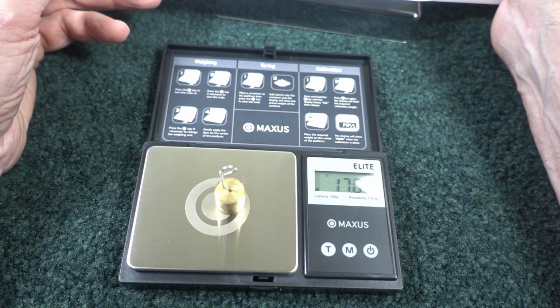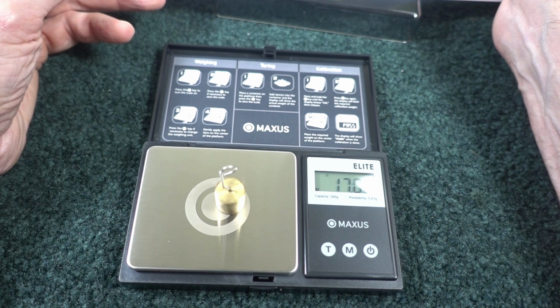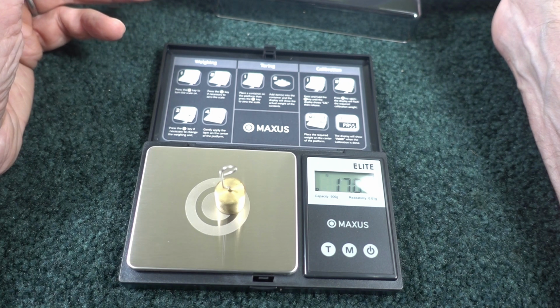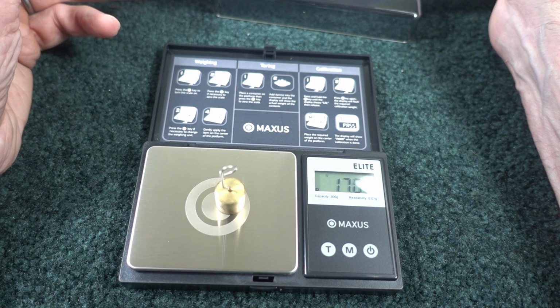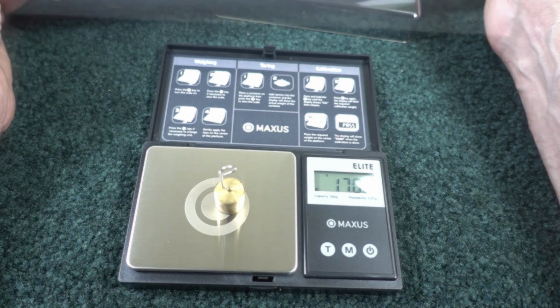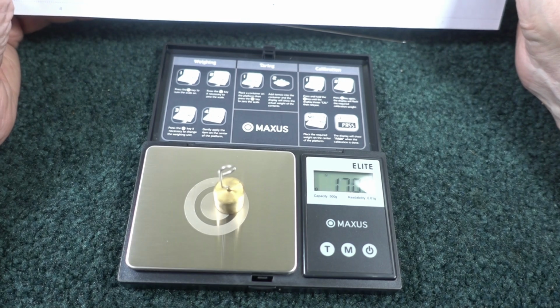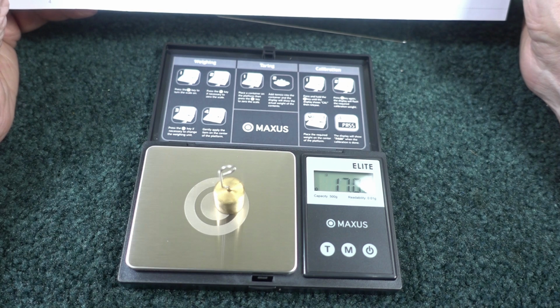Auto switch off occurs if the display shows 0 grams for 1 minute or if the display shows the same weight for 3 minutes. Auto backlight off occurs if the display shows the same weight for 1 minute. To maximize battery life, press the power key after use to switch off. So this will not weigh anything less than 5/100ths of a gram, and 5/100ths of a gram is the tolerance for this scale, plus or minus.